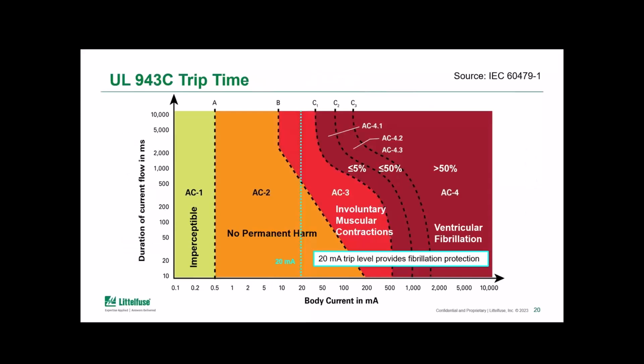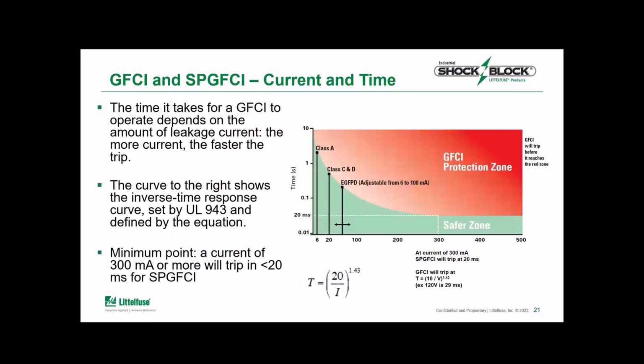So putting this on that curve that we reviewed previously, you can see that the 20 milliamp is above that let go threshold, but it still does provide protection from fibrillation and is required to abide by an ultra-fast reaction time that is specified in the GFCI standard. Now, the focus of some of the future slides here to talk about the ground monitor interrupter feature also helps to eliminate a lot of the shock events from happening in the first place. So it's still a major step forward in providing personnel protection on these industrial voltages.